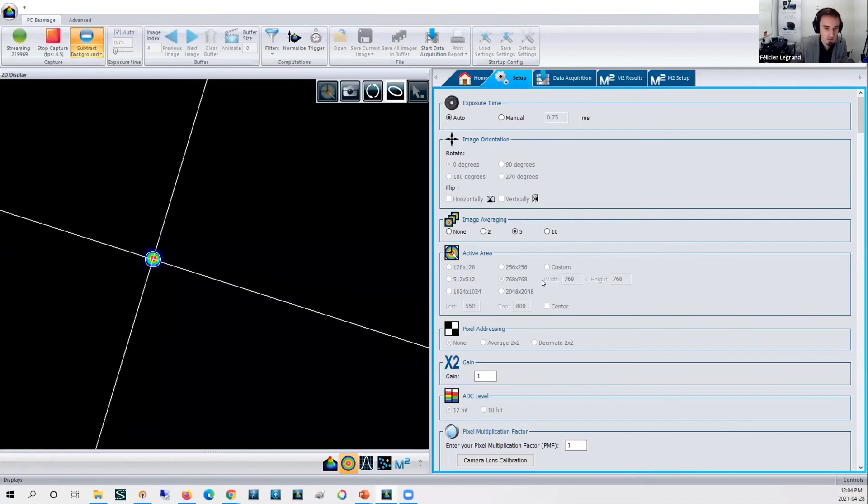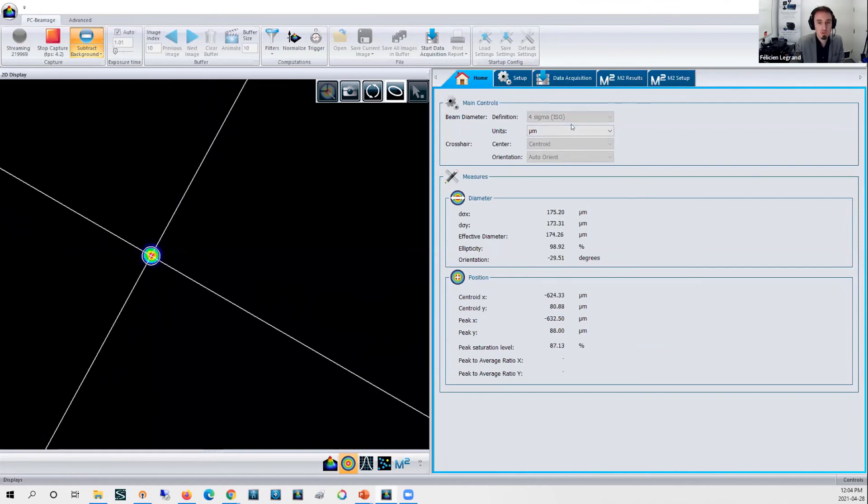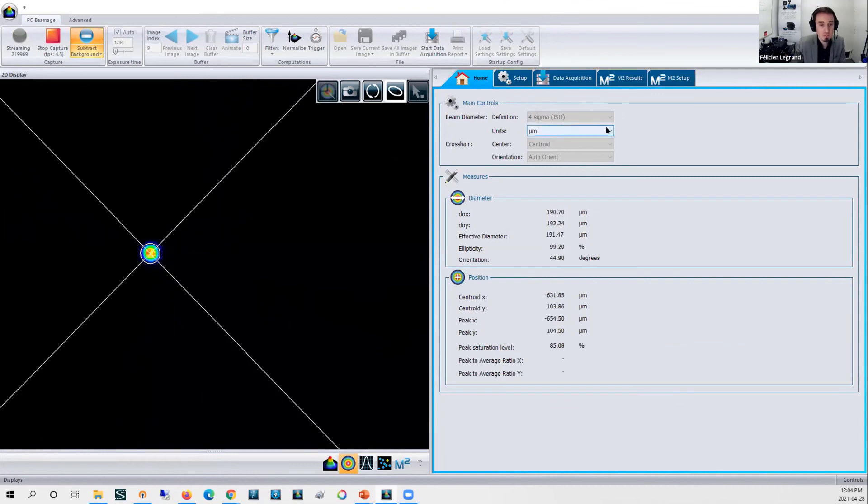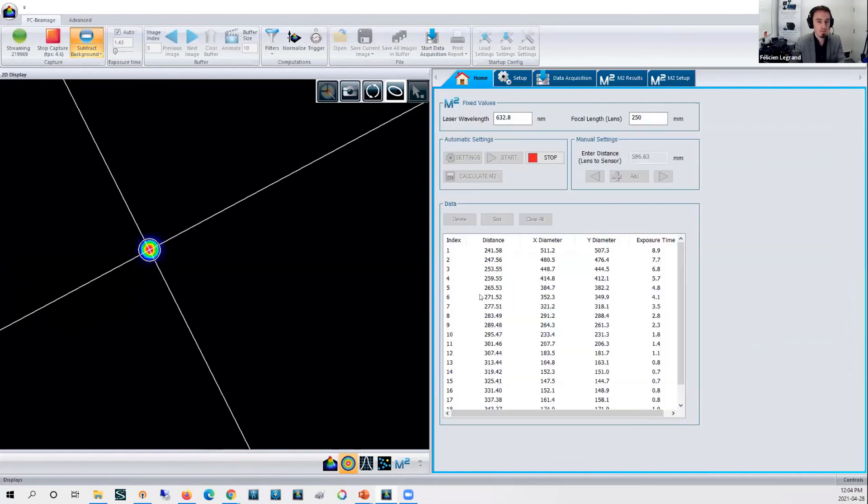But using a region of interest here, making the region smaller on the camera pixel area, that helps to get a little bit faster. I've selected this area here, pixel addressing not needed here and gain either. ADC level at 12 bit and so on. Home button here, we do provide four sigma ISO compliant measurement of the beam diameters. This is required to run accurate M² measurements. Units in micrometers, and you get a live measurement of those beam diameters here in X and Y, effective diameter, ellipticity, orientation and so on.